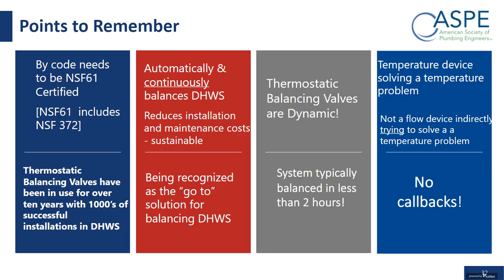So, some points to remember. By code, everything needs to be NSF 61 certified. Thermostatic balancing valves have been in use for over 10 years with thousands of successful installations in domestic hot water systems, so it's not cutting-edge technology. It automatically and continuously balances domestic hot water systems. It reduces installation and maintenance costs. It's sustainable. As conditions change, it will change to where it needs to be.